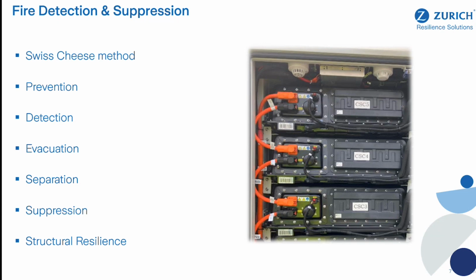So the one I like personally, which on utility scale battery storage sites makes the most sense to me, is this: whilst it's not inevitable that a battery container develops a problem, if it's separated from the next door container, I wouldn't say far away as in 200 meters, you've limited any problems to one container. So the NFPA came out with a value of 3 meters separation between one container and the next. There can be some small changes to this. For instance, I think if there's a 2-hour firewall either between two containers or built into a container, they can be positioned closer to each other. But a general rule of thumb is a minimum of 3 meters.